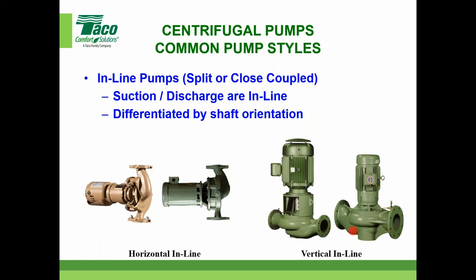So that's one of the big possibilities is savings there. Number two, you can change the seal for this. This one here, you got to pull the motor out, right? You got to pull the motor out. So again, the other one I said, that was our CI model on the base mounted. You shouldn't get much bigger than 10 horse. For these, I mean, they go up to 60 horse again, but these split coupled ones, you don't have to touch that motor at all.